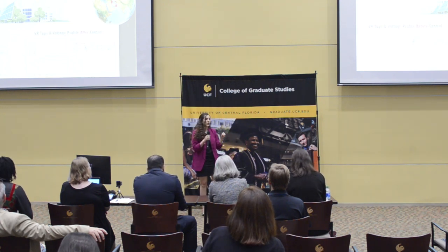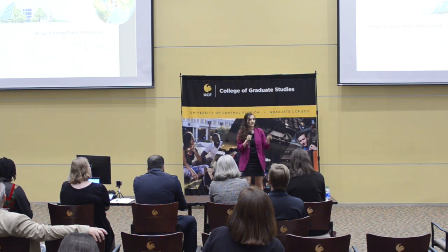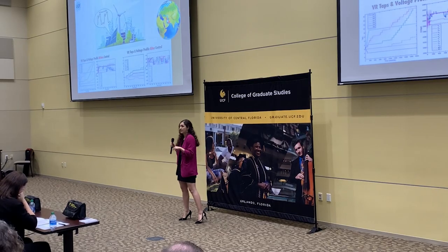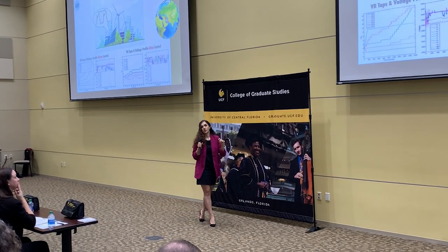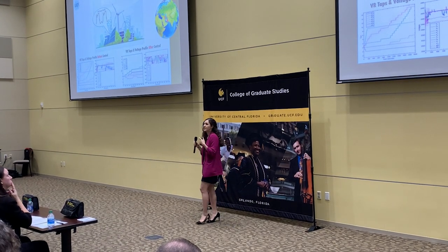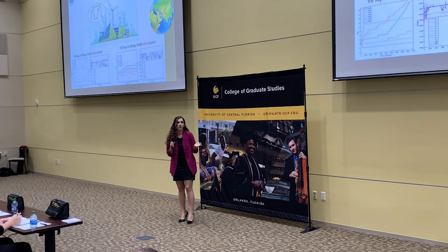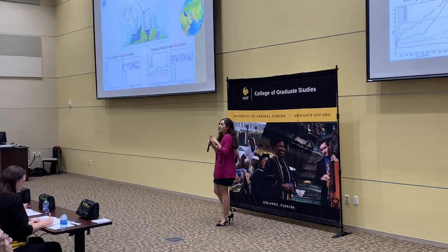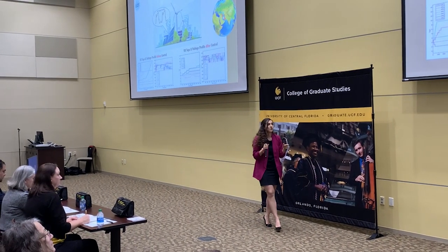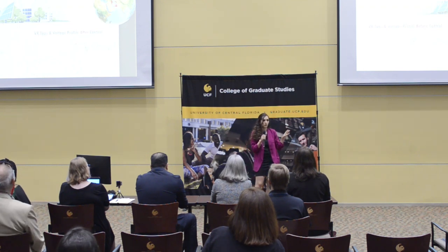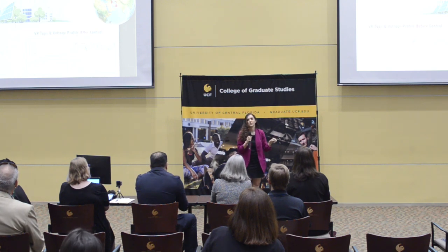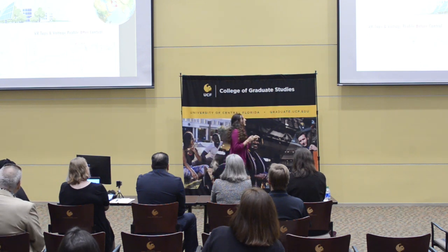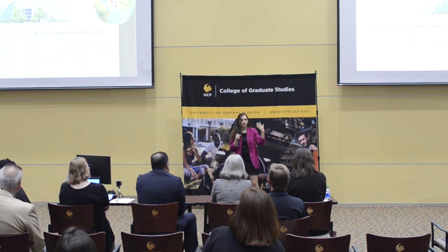This control method can determine the number of taps for voltage regulators and capacitors. It can determine which voltage regulators or capacitors should act first, and also it can determine the reactive power generation for each DG. We have implemented this control method on several test systems and got significant results. As you can see on the slide, after we apply our control, we have a unified voltage profile, which means we keep the voltage inside a specific threshold, and we also minimize the number of taps for the voltage regulators and capacitors, which extends the life expectancy of these devices.